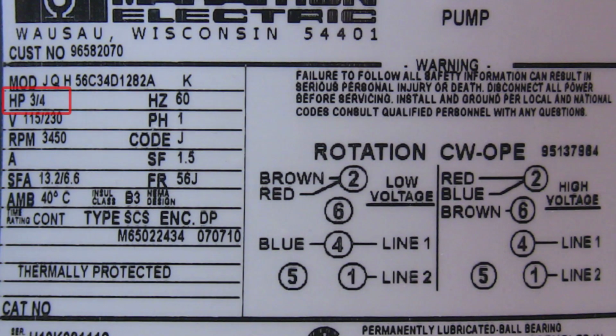Although there are many pieces of valuable information contained here, there are about 6 which are vital to know. Horsepower. The horsepower is an indication of the motor's strength and is related to its power consumption. Always replace motors with the same horsepower value. The voltage of the motor is listed as either a single or double value. In this case, the 115-230 indicates the motor is capable of operating with either 115 or 230 volts, depending on how it's configured internally. The first number listed is referred to as the low voltage, while the second number is the high voltage. The terms low and high only refer to the order the numbers appear and are not related to the amount of power involved.